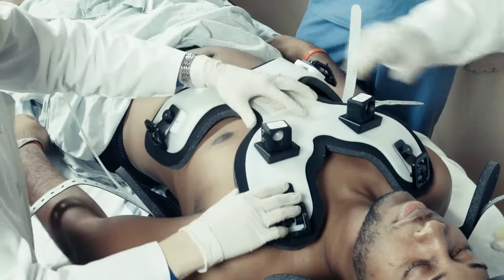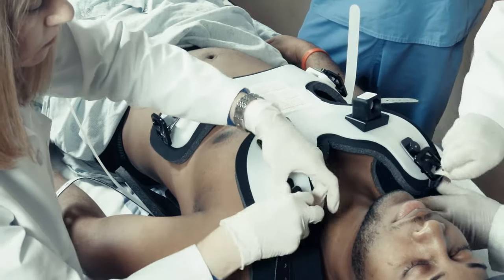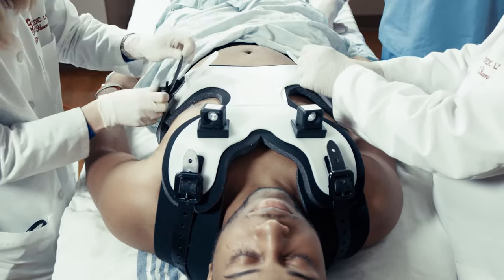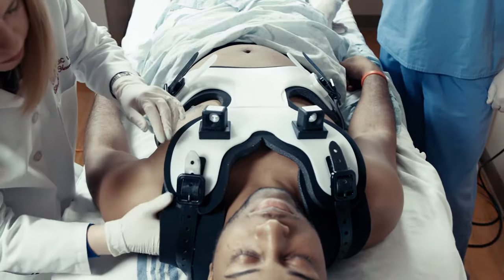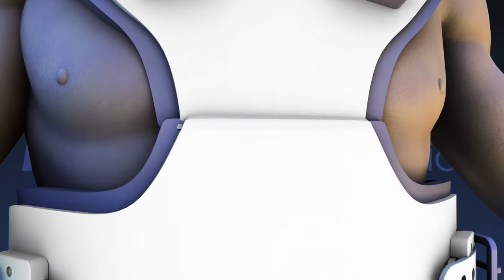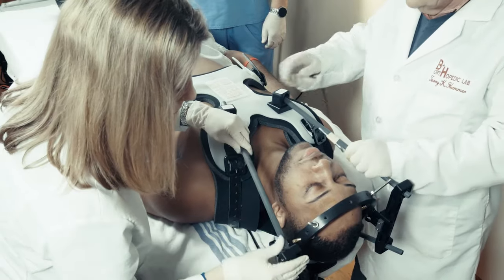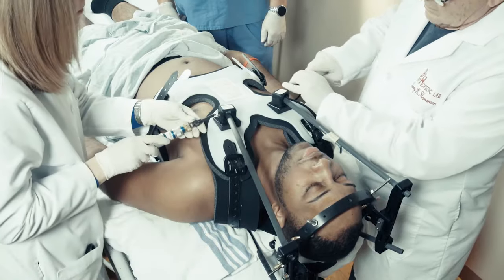The anterior portion of the vest is connected at the sides and over the shoulders to the posterior shell, engaging the interlocking tabs. The vest should be pulled snugly around the waist. The shoulder straps should be adjusted to allow one hand to fit between the vest and the patient's shoulder. The anterior shell possesses a breakaway seam or cardiac crease for CPR at the xiphoid line. All of the nylon balls on the vest and head holders are loosened. The anterior rods are slid caudad from the head blocks through the vest. Rods should not extend further than the vest anteriorly.